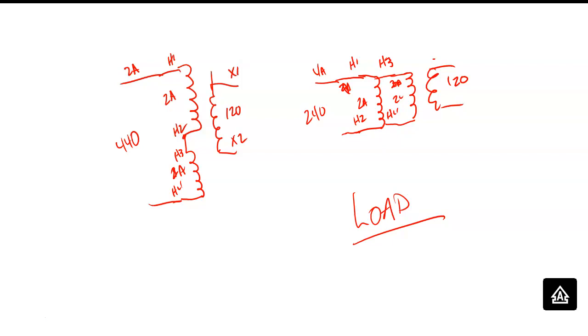So no, the coils have nothing to do with power. Power, what determines power? Now the transformer's got to be rated at a current that can provide that load, right? You understand? So currents are rated, they're not rated in watts. Currents are rated in usually kVA, especially industrial transformers. Kilovolt amperes, because this has got to deliver what we call apparent power.